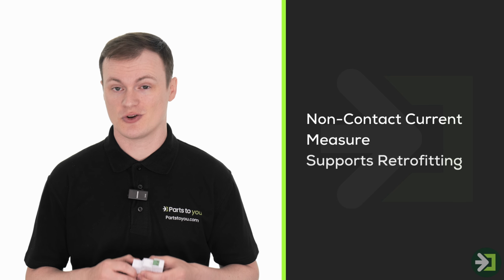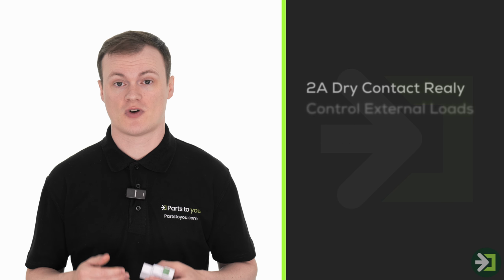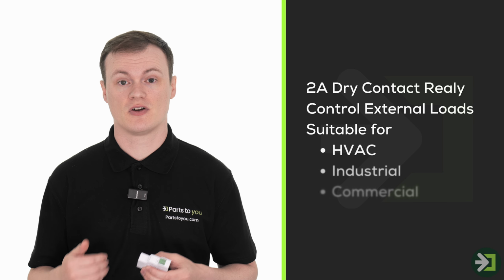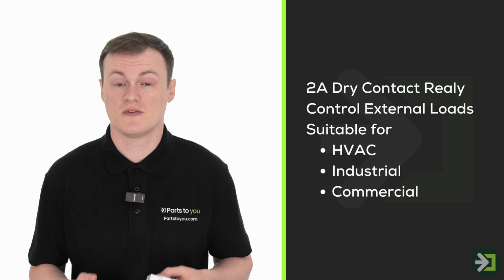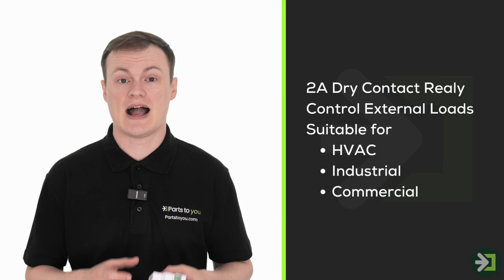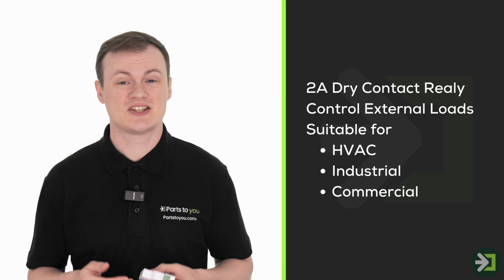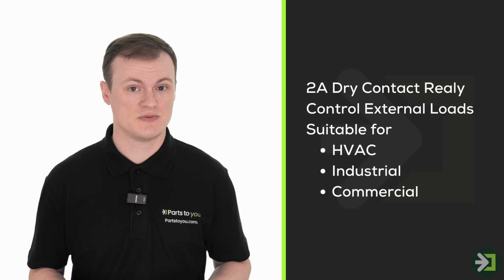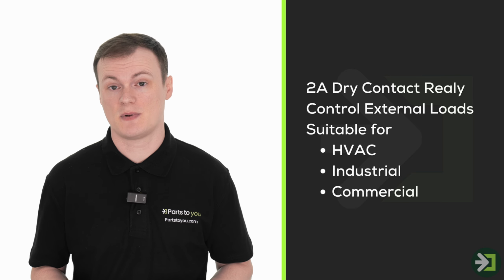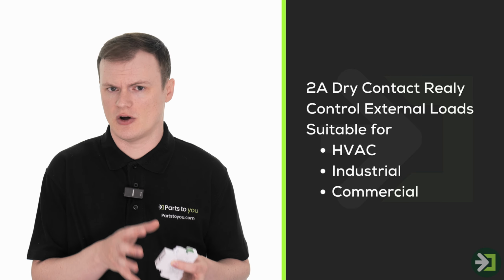And then there is the control layer. The built-in 2-amp dry contact relay can be used to drive a contactor, meaning the system is capable of controlling larger loads safely and indirectly. This is especially important for HVAC systems, industrial equipment, or any application where you would never route load current directly through a small device.